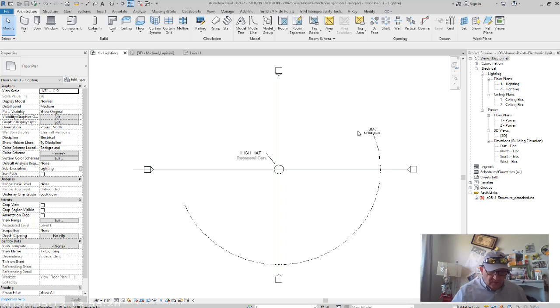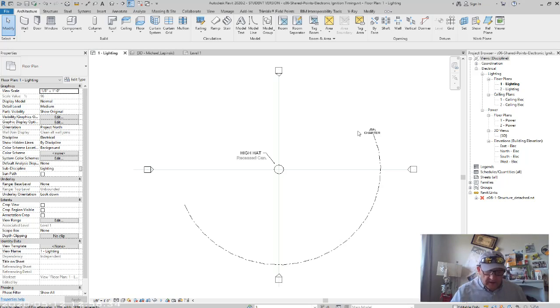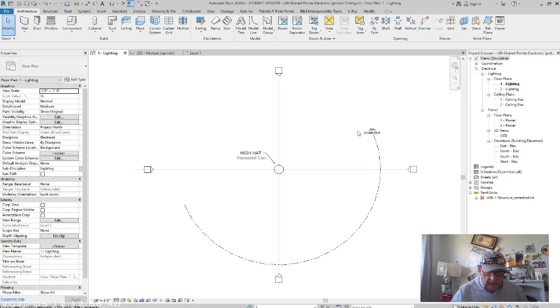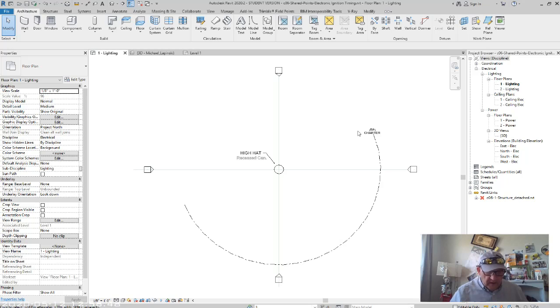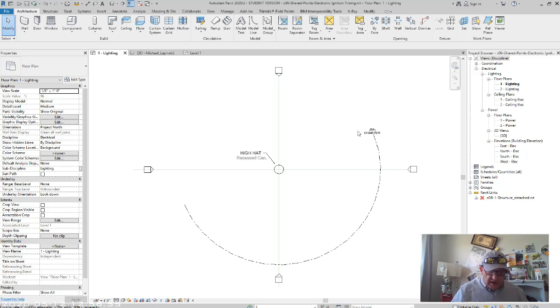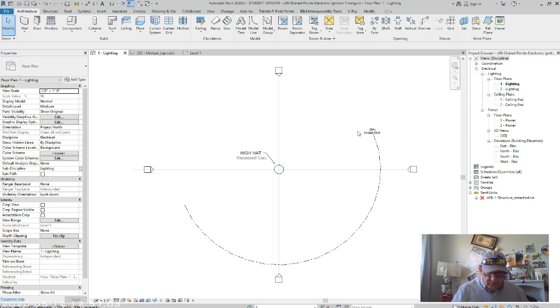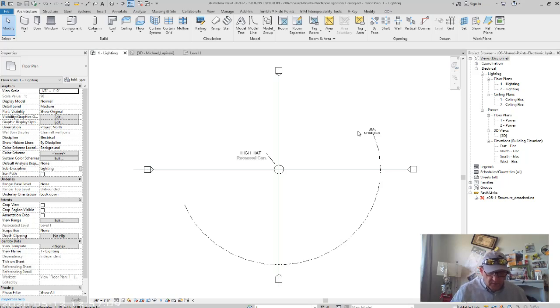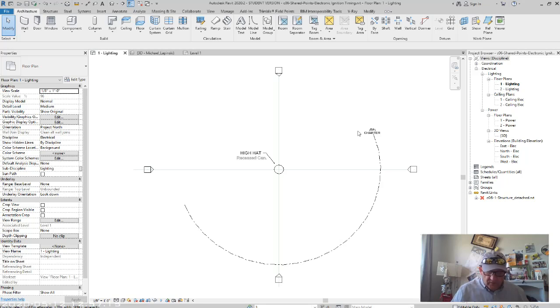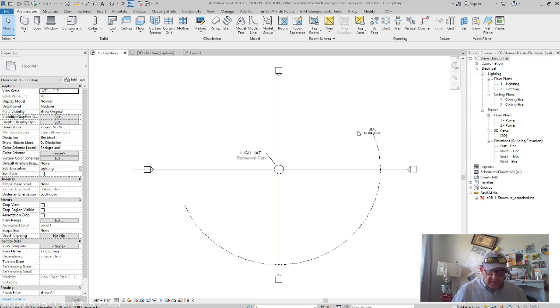In addition to the work set loading control, you can apply visibility settings automatically to linked models. As long as the work sets in any linked files are named exactly as they are in the host file. For example, if you linked a model that had the default work set named Shared Levels and Grids and your host model also had the same work set, you can hide the work set in both the host and linked model in one step. Open the Visibility Graphics Overrides dialog box, select the Work Sets tab, and then set Shared Levels and Grids to hide. You will see that any data objects assigned to that work set in either the host or linked model are hidden. You do not need to perform a separate visibility override on the linked file.